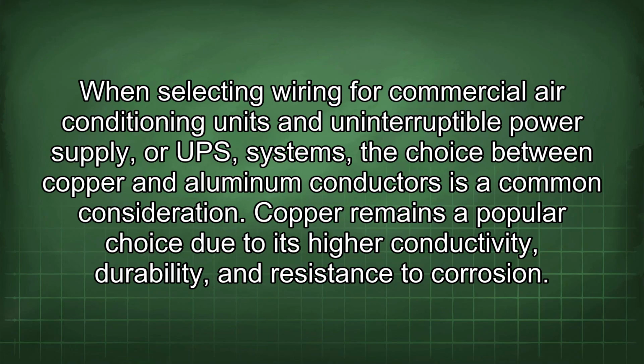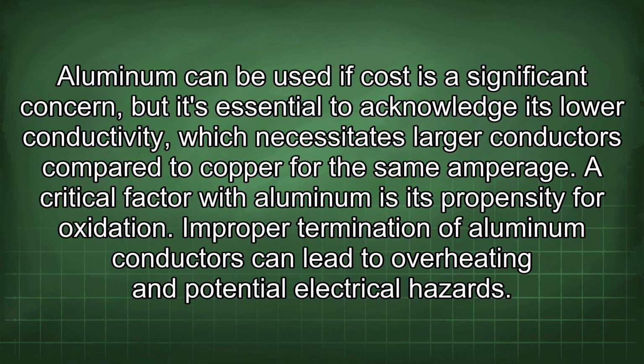When selecting wiring for commercial air conditioning units and uninterruptible power supply, or UPS, systems, the choice between copper and aluminum conductors is a common consideration. Copper remains a popular choice due to its high conductivity, durability, and resistance to corrosion. Aluminum can be used if cost is a significant concern, but it's essential to acknowledge its lower conductivity, which necessitates larger conductors compared to copper for the same amperage.